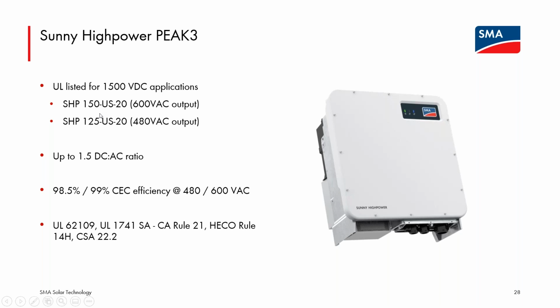at high power levels. My understanding is that code may be different in Canada versus the US. In the US, the inverter itself is rated up to 1500 volts. There is not an allowance for anything over 1000 volts on a commercial rooftop in North America. These machines really do need to be working with arrays that are strung up to 1500 volts. So that is one disqualifying factor for using on a rooftop down in the US. The other one is there is no AFCI built into each inverter. So that's a second disqualifying situation for rooftop applications.